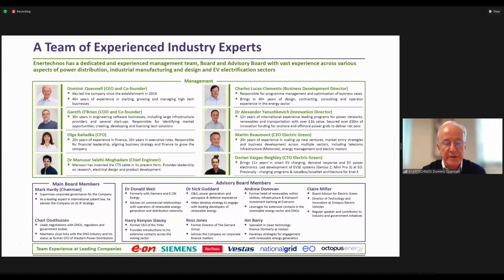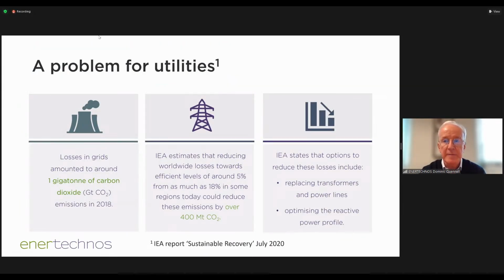And what I want to talk about is a problem that confronts utilities, and that is losses in grids, which amount to, according to the IEA Sustainable Recovery Report, around 1 gigaton of CO2 emissions every year. And the IEA estimates that if we could bring losses worldwide towards a level closer to 5%, we could reduce that by about 40%, or 400 megatons. Among the things that they suggest could be done are replacing transformers, replacing lines and cables as they need to be replaced at the end of their useful life, and finally optimizing the reactive power profile.